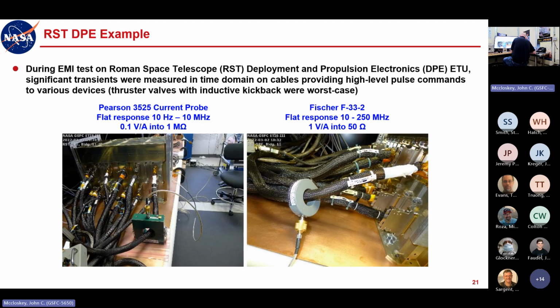We have the standard current probes for scopes with the very small window. That obviously wouldn't work here. So you either need one of those gun type probes with like a 1-inch aperture, or you've got to use one of these. And if you're using one of these that's not specifically the gun type probe, you've got to take the transfer impedance into account.